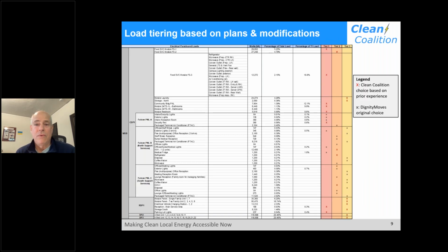The load tiering requires you to really be cognizant of what all your loads are. This is basically a breakdown of all the electrical panels across the site, which all start at the main service, go out to distribution panels, down to circuit breaker panels, and ultimately down to the actual loads you're serving - the appliances and so on. On the far right are three colored columns representing tier one, tier two, and tier three loads. We tier all the loads, then figure out how much power and energy capacity is required to make sure the tier one loads always stay on. That's very fundamental to the way we design our solar microgrids.